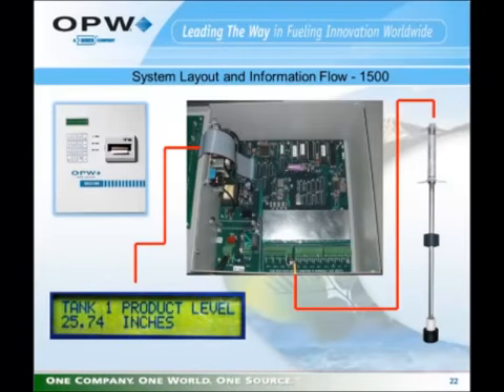Looking at the EECO 1500, it's a fairly simple layout. There is a single main board in the unit. On that main board is the interface for all probes and sensors in the intrinsically safe section. On the main board are the leak sensor communication circuits, the tank probe communication circuits, relay control circuits, and processing, all on one board. There is a separate power supply that is mounted on the chassis of the unit. There is also a second power supply on the main board. The power supply on the main board is only used for probe voltages. So you see in a simple form, the probe in the tank feeds data to the probe connection on the main board, which then gets fed and processed in the main board and out to the display and the printer.